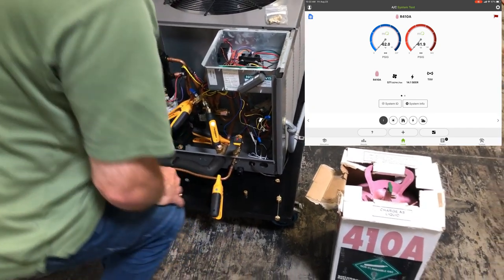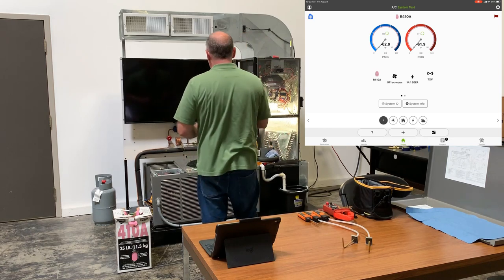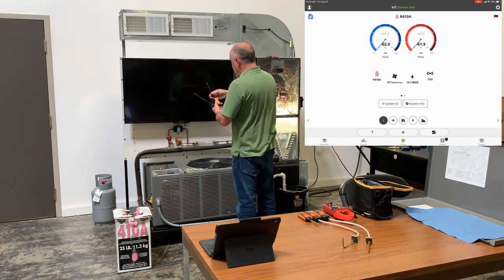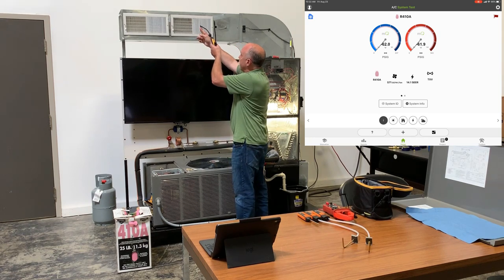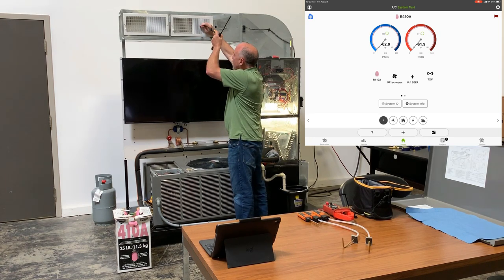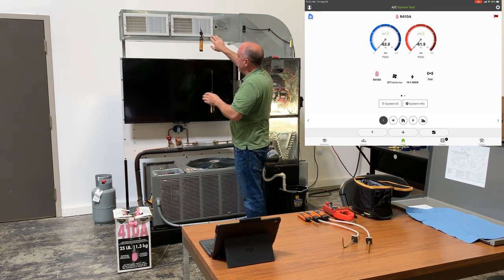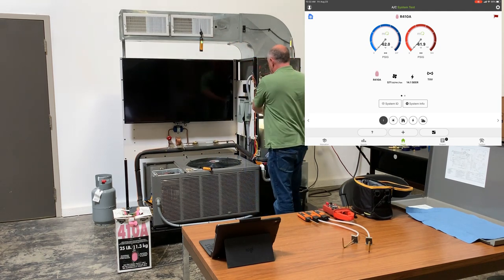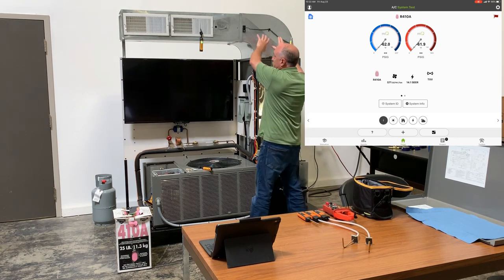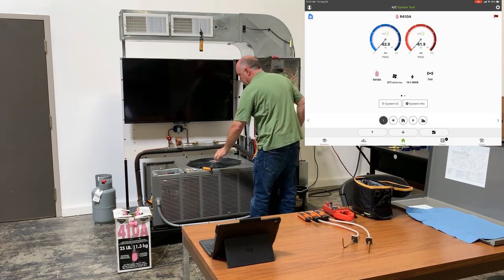Now I've got all those probes hooked up and ready. Next is the supply air probe. I can open a register up just a tiny bit and slip the probe in between and get it inside. I want to get into the airstream as far as I can — I don't want to be right on top of the air handler or right on top of the coil. I want to give it air where it's had enough time to go through the blower, mix well, and I get a good supply air temp.